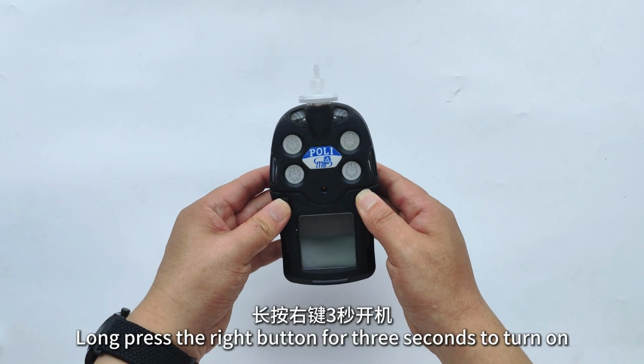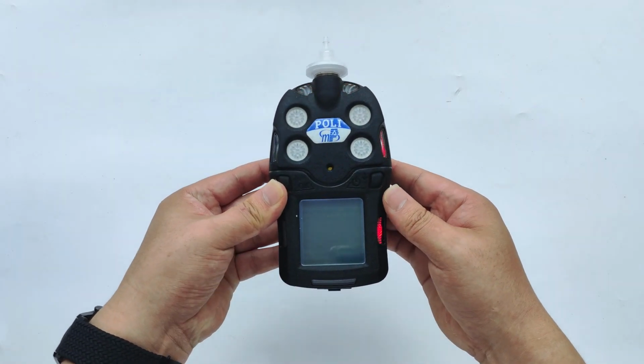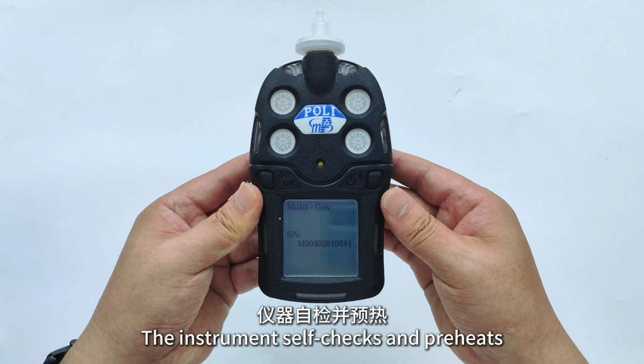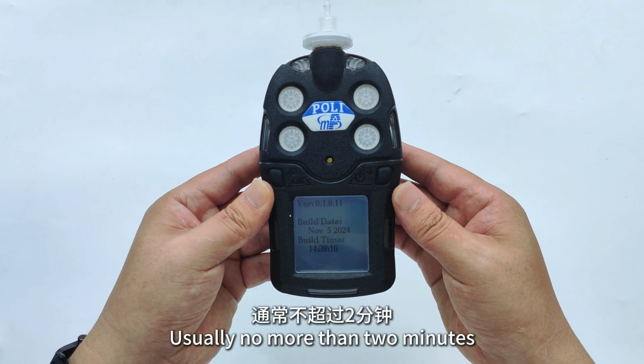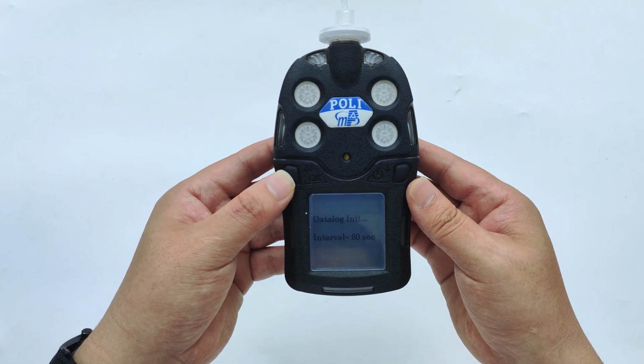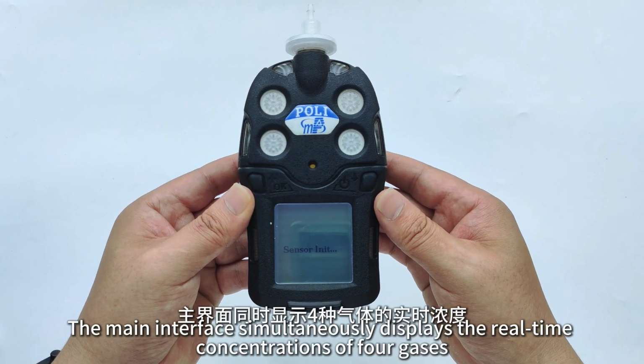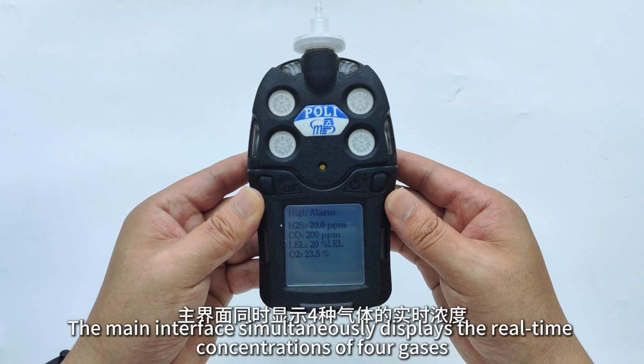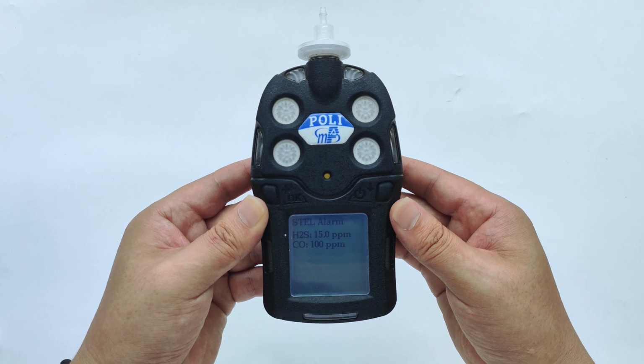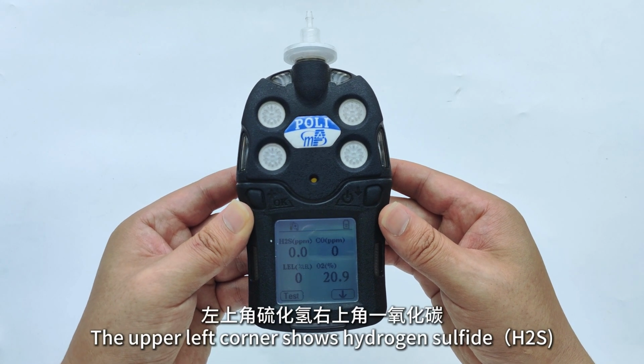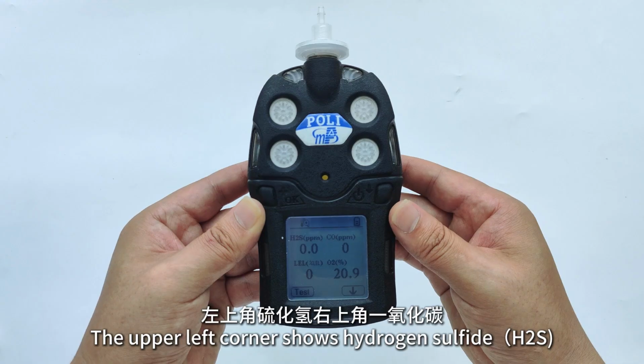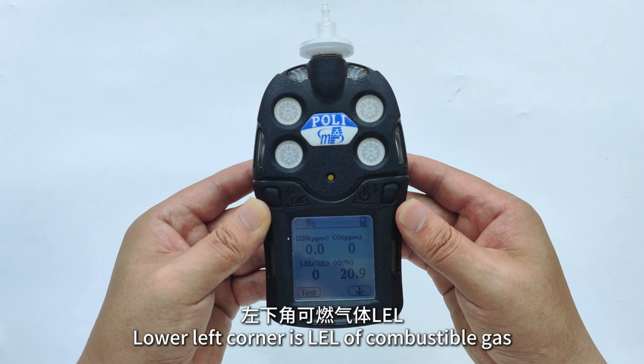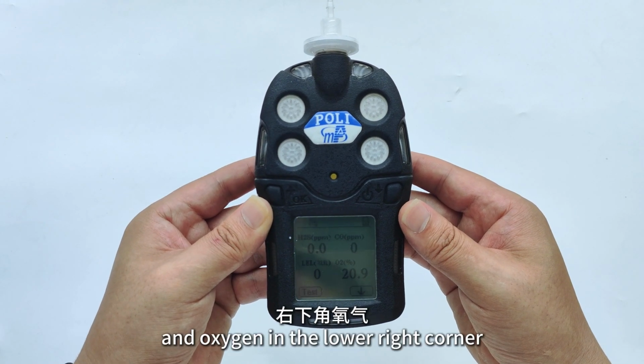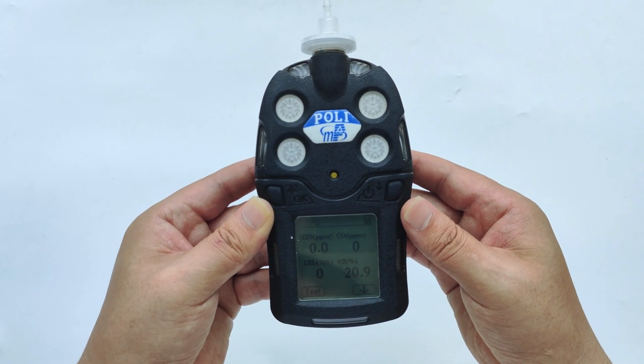Long press the right button for 3 seconds to turn on. The instrument self-checks and preheats, usually no more than 2 minutes. After the preheating is complete, the main interface simultaneously displays the real-time concentrations of 4 gases. The upper left corner shows hydrogen sulfide, H2S. The lower left corner is the level of combustible gas, and oxygen is in the lower right corner.